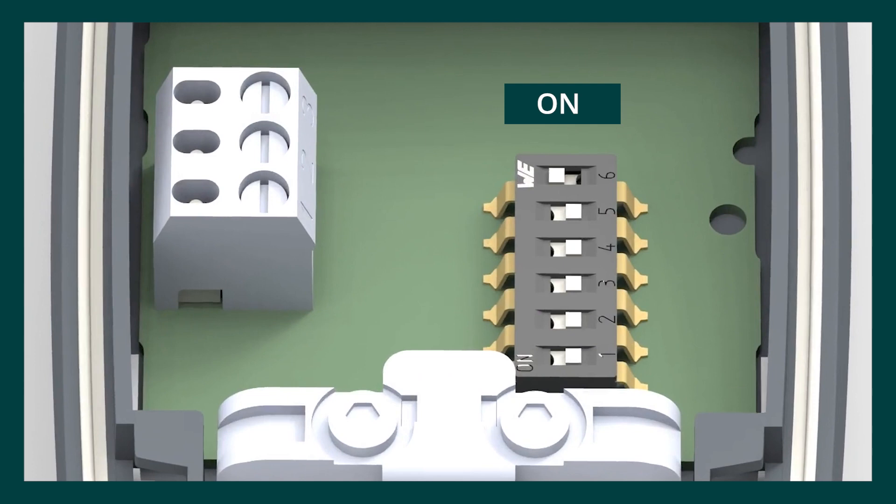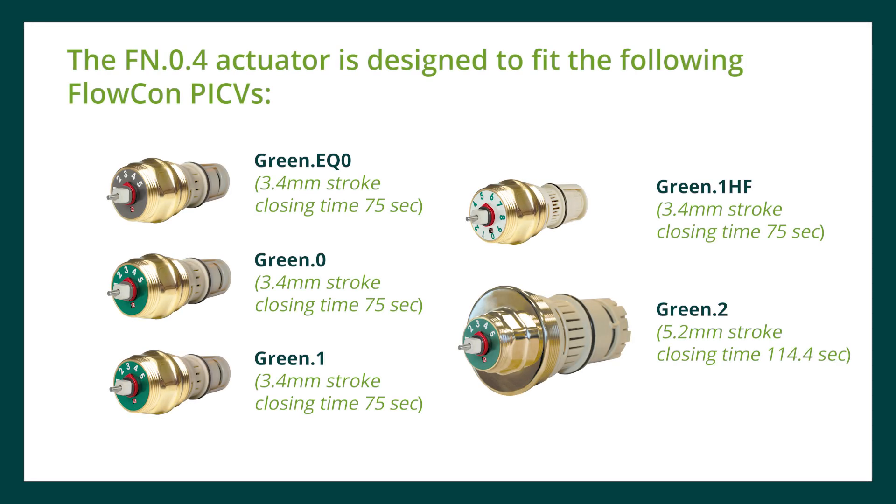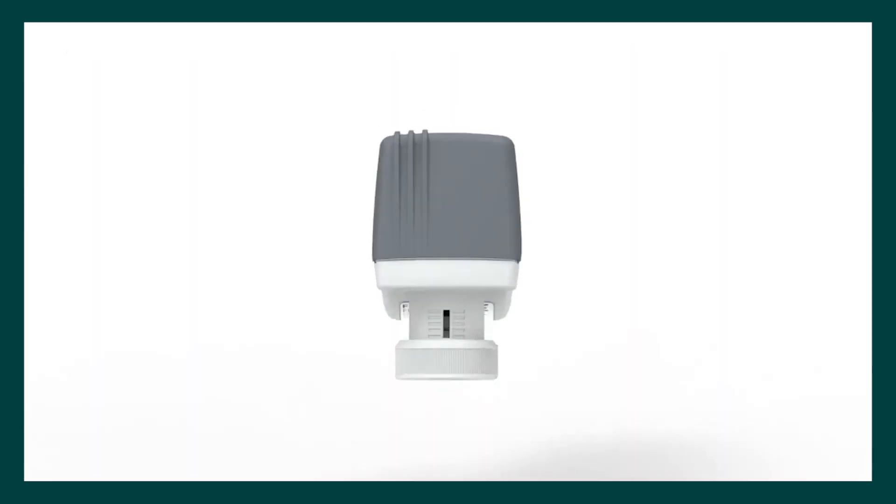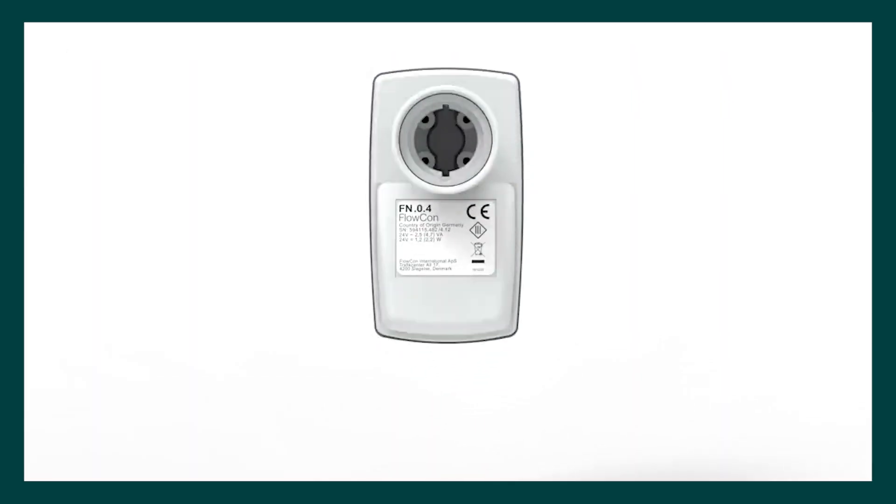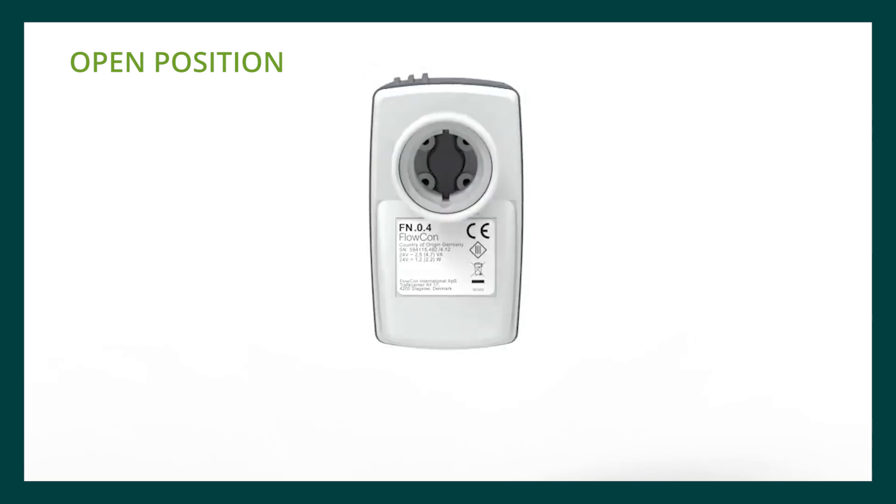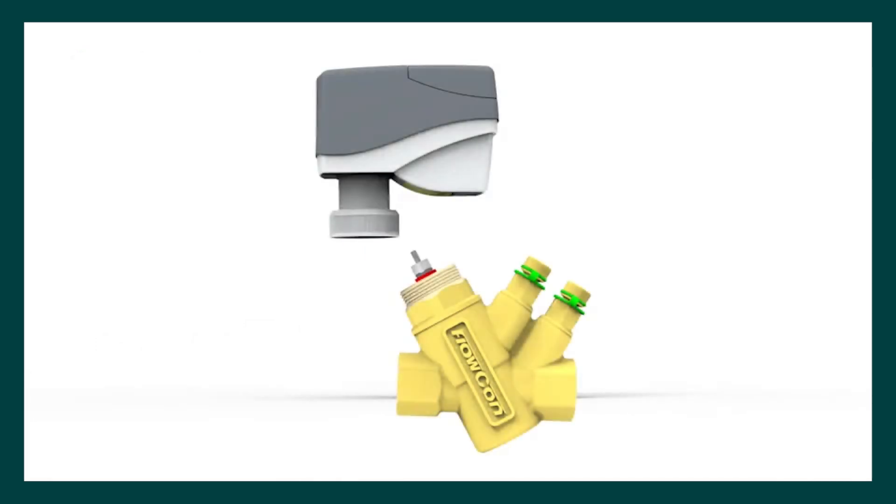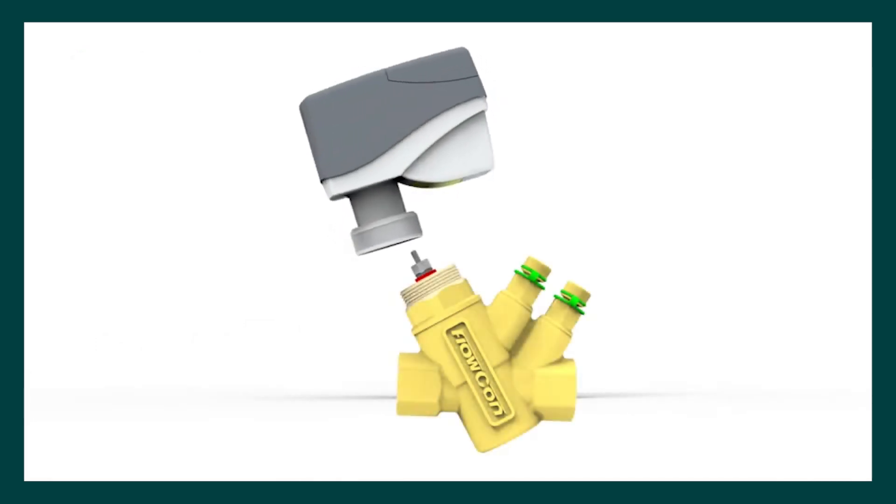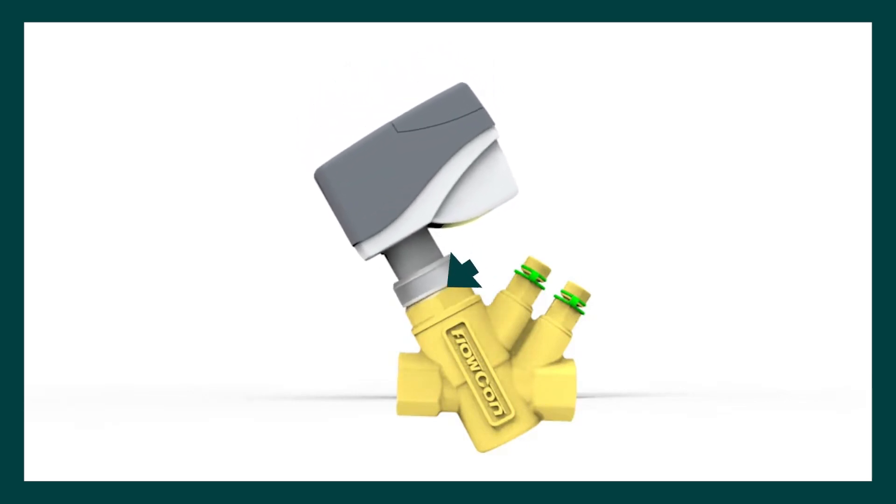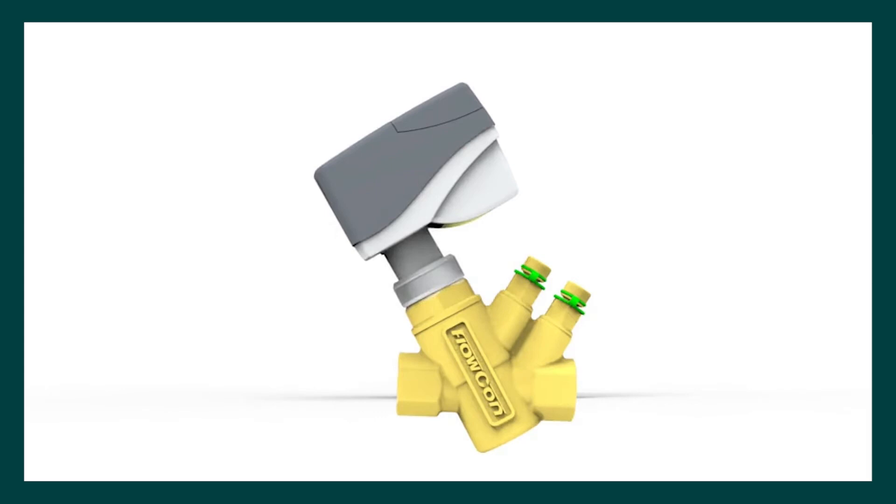The FN04 actuator is designed to fit the following FlowCon PICVs. Ensure the actuator is in the fully open position before mounting it on the valve to avoid the risk of damaging the PICV. Align the actuator to the PICV threaded insert. Rotate the locking ring clockwise by hand until hand tight. The actuator is suitable for mounting upside down, but we recommend mounting the actuator above the horizontal body facing upwards.